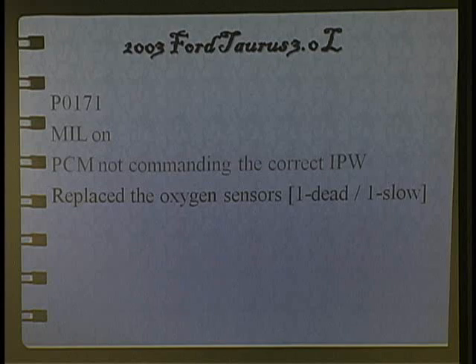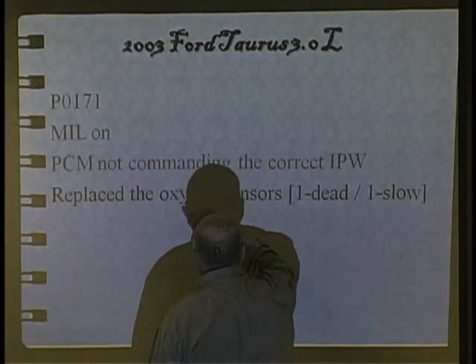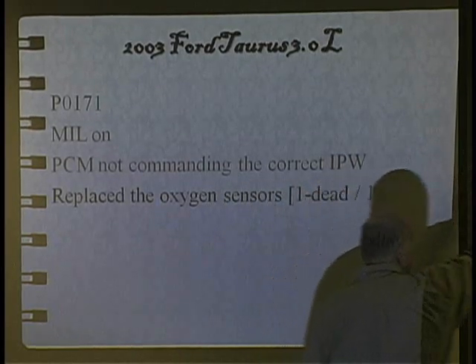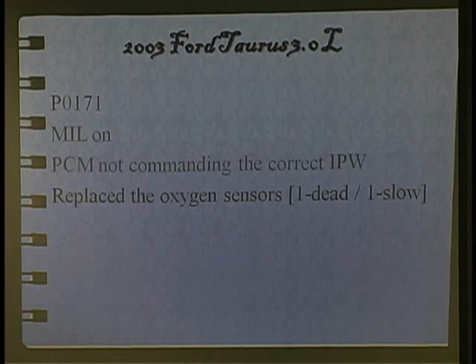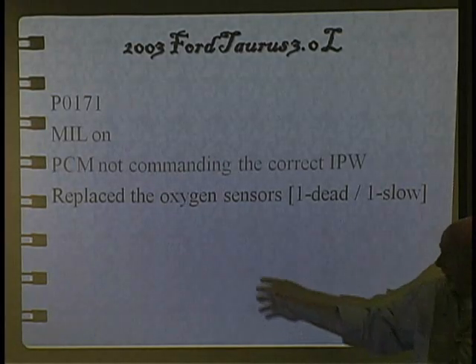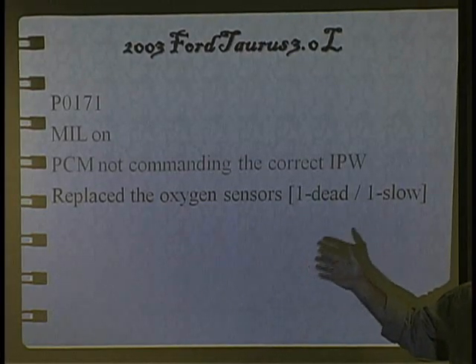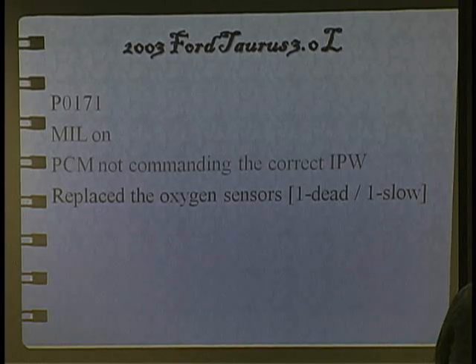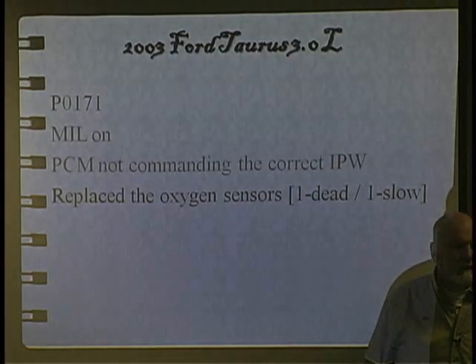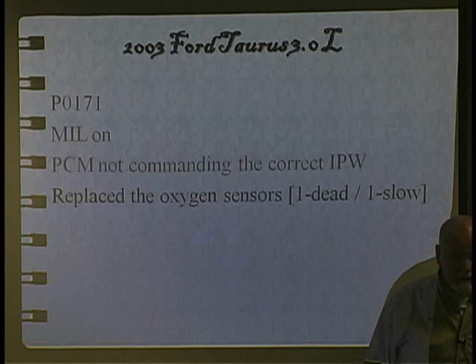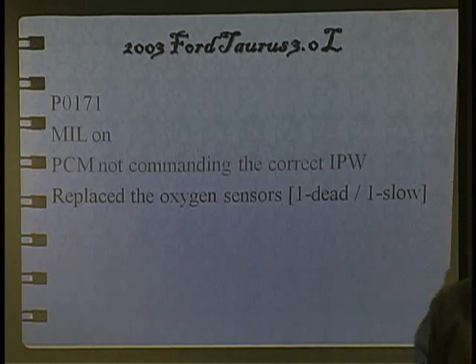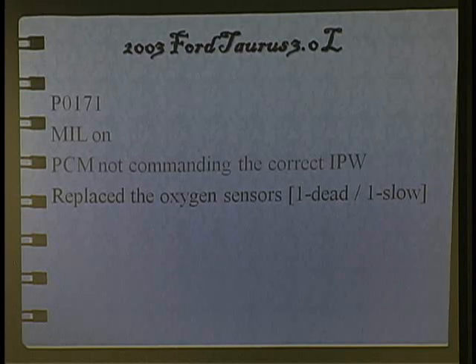Cross counts is a digital binary counter. It starts at 0. If you could look at the raw data of cross counts, it would count 0, 1, 2, 3, 4, 5, 6, 7, 8, 9, 10, up to 256, boom. So when you see cross counts on a diagnostic test mode 1 scan data, you don't know where they are in the stair. You have no basis to establish what's at 9 of. Is it 9 from the beginning, 9 from 10? So cross counts aren't what we think they are. They're digital binary counters. If you have a diagnostic test procedure that uses cross counts and it works for you, good. Keep using it. If it's ever screwed you up, stop using it.